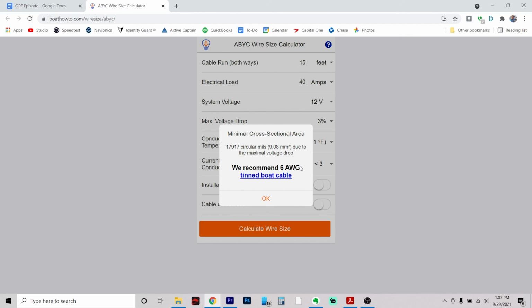That's the size of the wire to connect this one circuit. In order to fuse that appropriately, we're going to just take the max amperage of the circuit and we're going to increase that by anywhere from 125% to 150%. 150% of 40 amps is 60 amps. So we're gonna go with a 60 amp fuse. Now that's pretty simple for a relatively small load like the DC to DC converter.